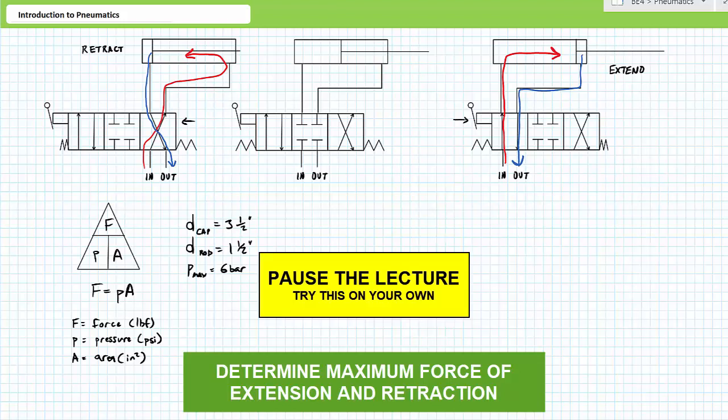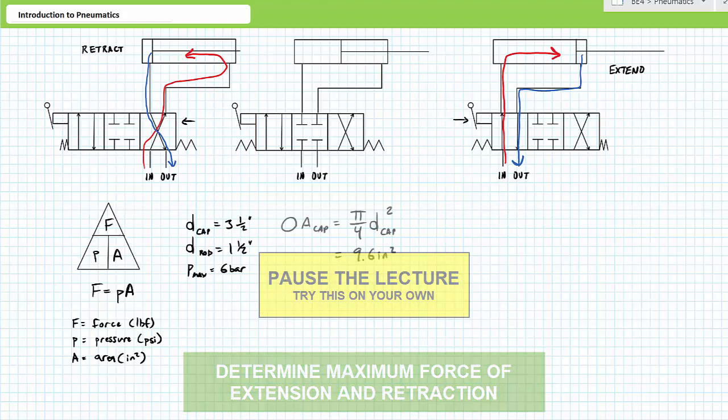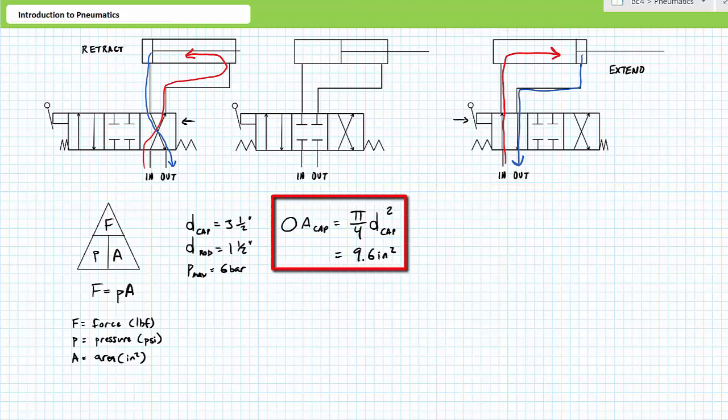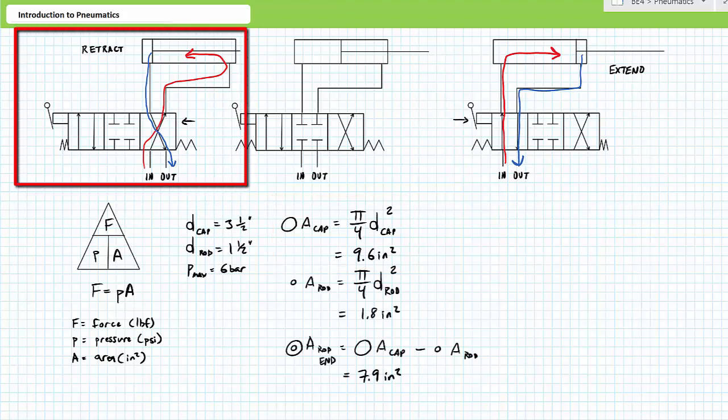If you're tracking, you should have obtained the following results. Extension necessitates pressurized fluid into the cap end port and the rod end port be exhausted at low pressure. During extension, pressurized fluid acts on the full cap end area. The circular cap end area is equal to π/4 times the diameter of the cap squared. Substituting our values results in a cap area of roughly 9.6 square inches.